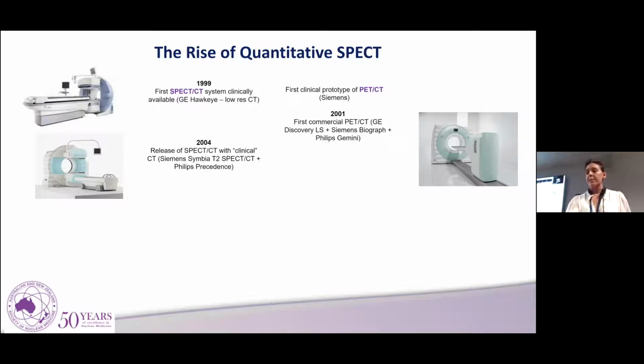Now, obviously, there's some fundamental differences between the SPECT and PET modalities. For example, we know that PET has a superior sensitivity when compared to SPECT. This relates to things like the improved signal-to-noise ratio of our reconstructed data. It also means that we can take that sensitivity back to imageable activity in the field of view, which of course relates to things like acquisition duration and also patient dose.